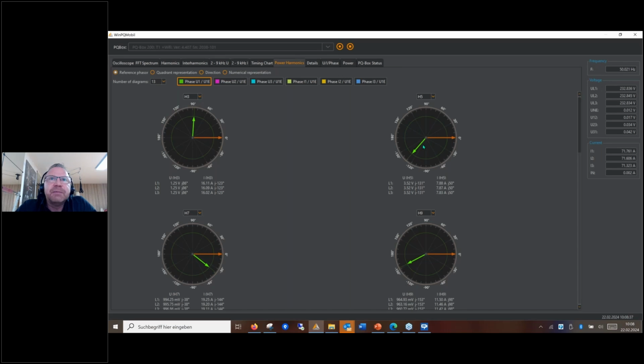So the phase angle is at the moment not so interesting, but now I switched on a producer of harmonics. So here I have a big producer of harmonics. It is producing 7.8 amps, also the fifth harmonic. But now we can easily get a feeling: is this machine positive or negative for the grid? So here is an interference in our network. And if I switch on this machine, it is producing 7 amps, but exactly 180 degrees opposite. So this machine will work like an active filter.